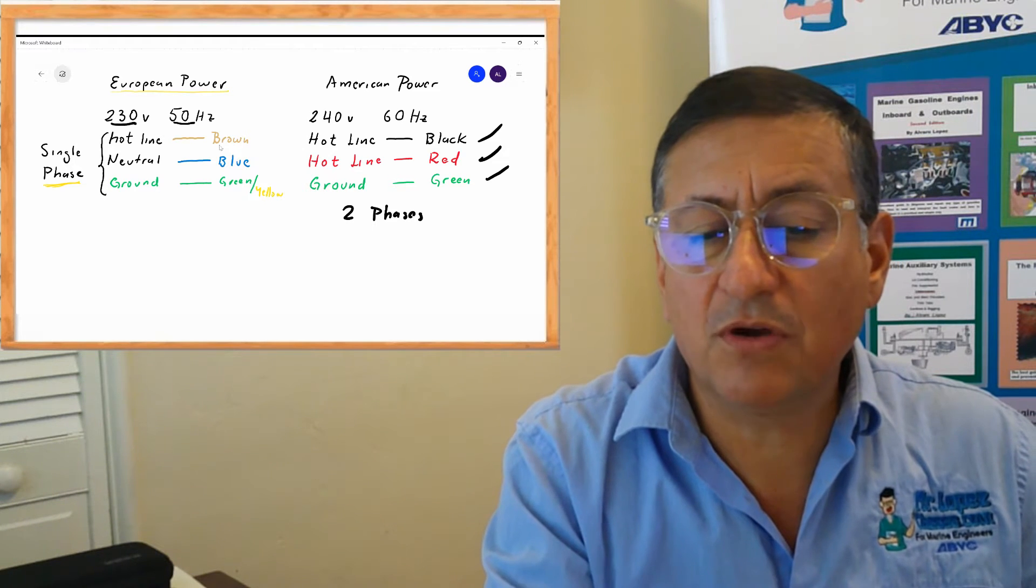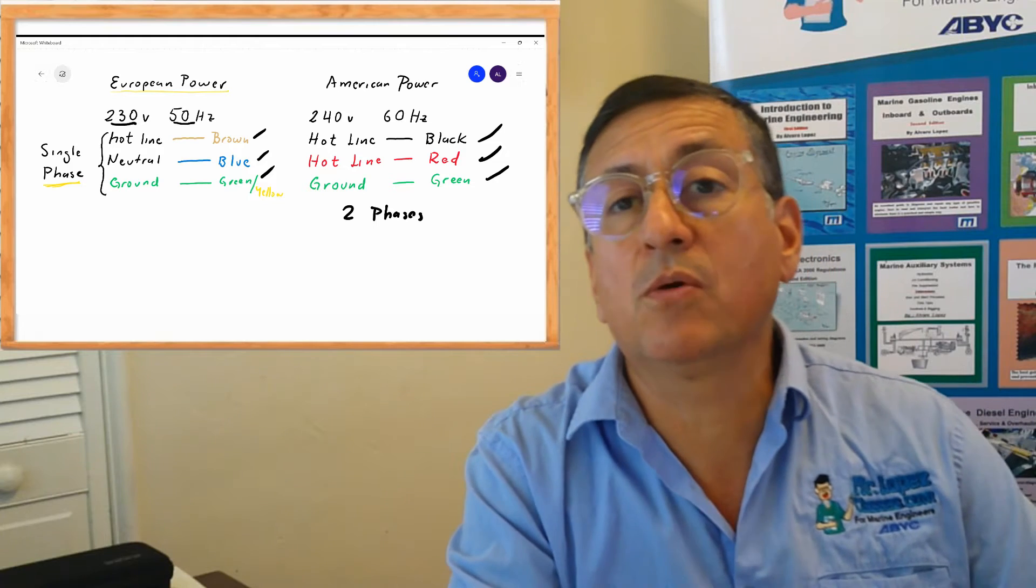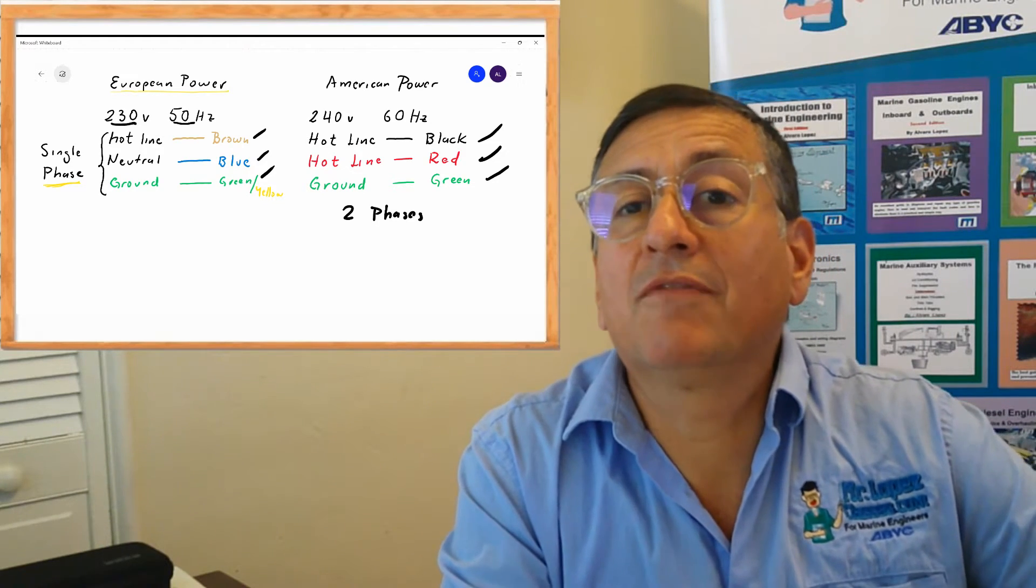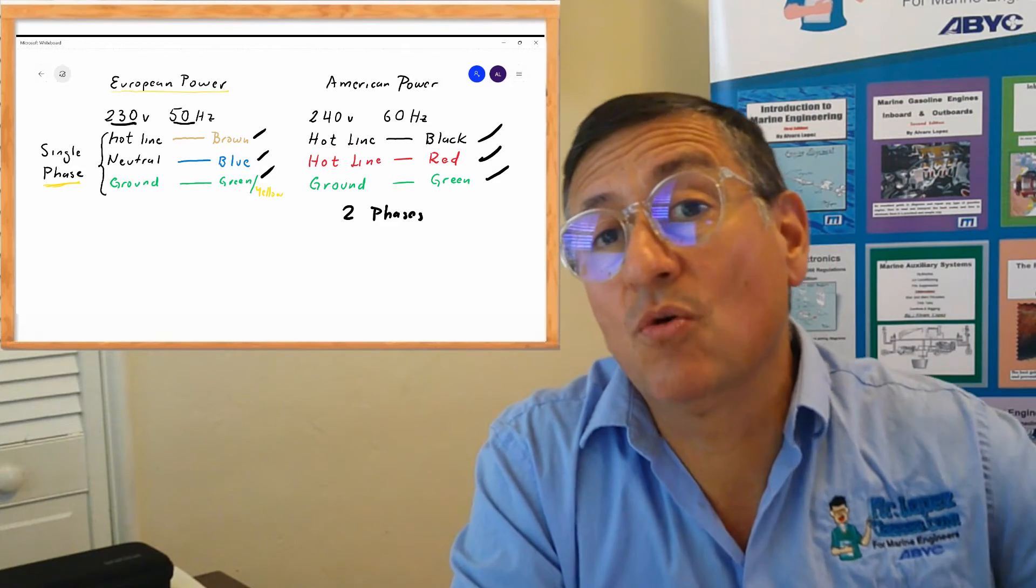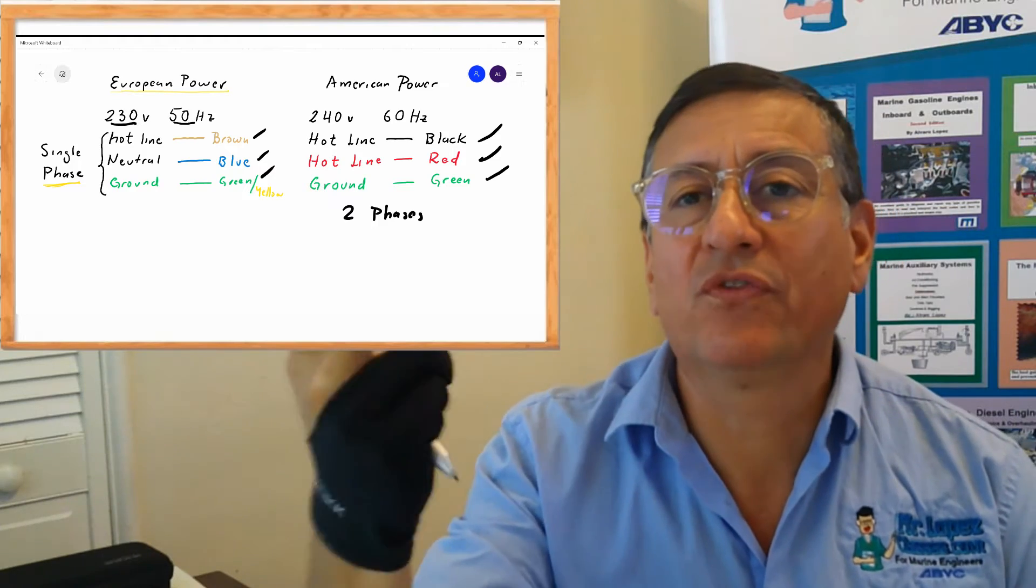In European power, single phase, you have brown for hot line, blue for neutral, and green with yellow strip for ground. That's different. You have 230, 50 hertz in one phase, and you have 240, 60 hertz in two phases.